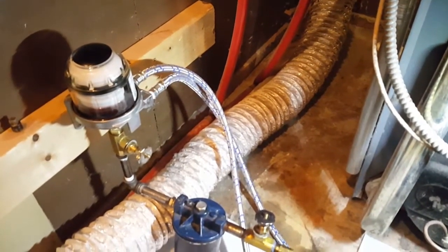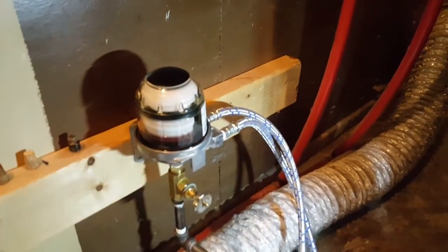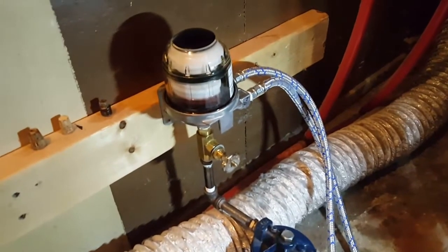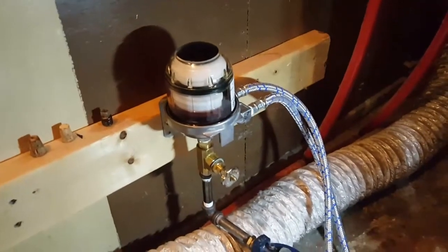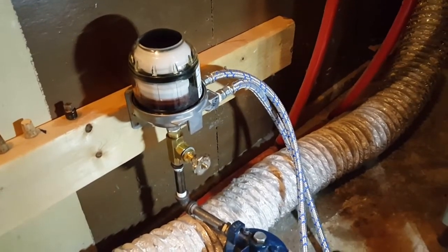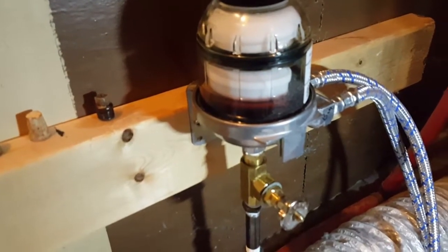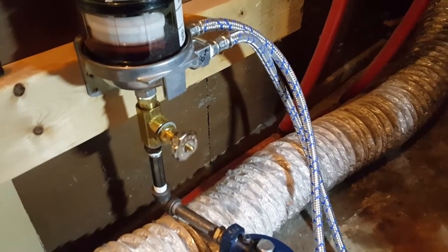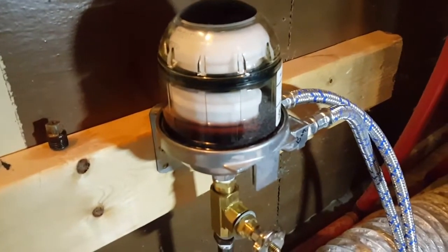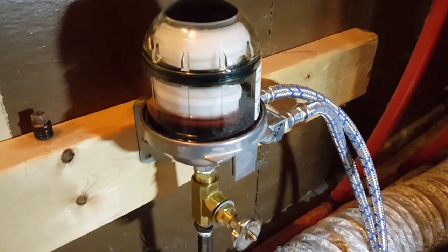Right away I was impressed — I didn't have to prime anything. I just turned the boiler on and you could watch the air bubbles being bled out through here. I didn't even have to prime it. It self-primed, self-bled, and fired right up. Now it's just maintaining.